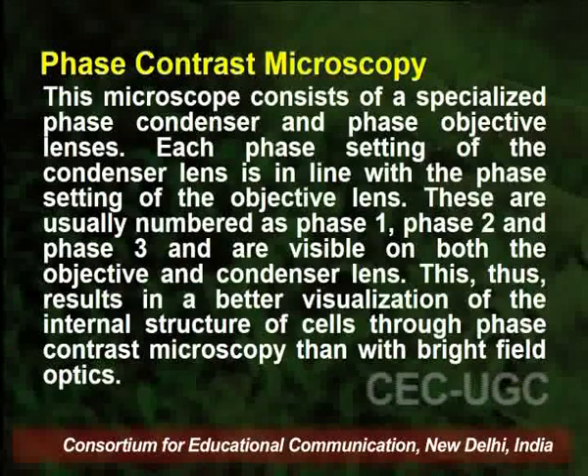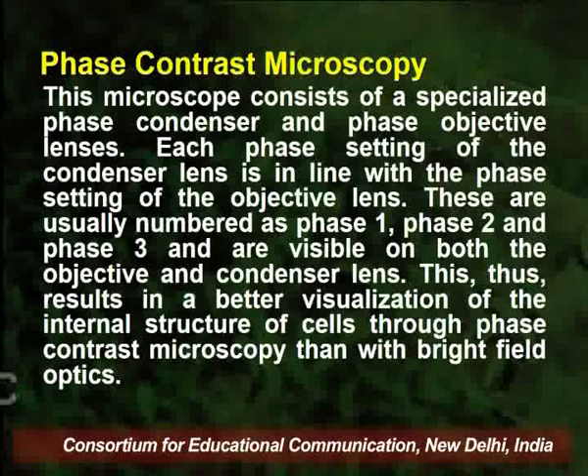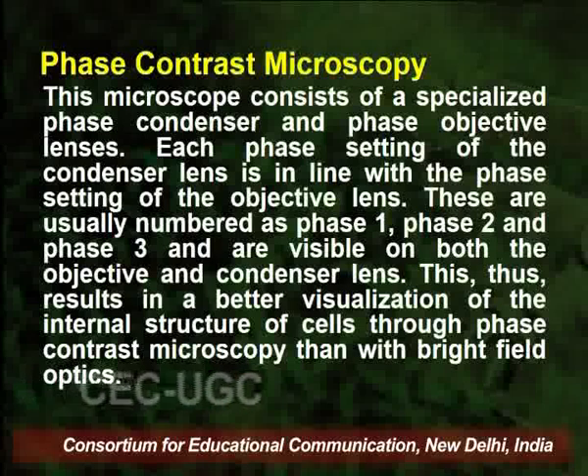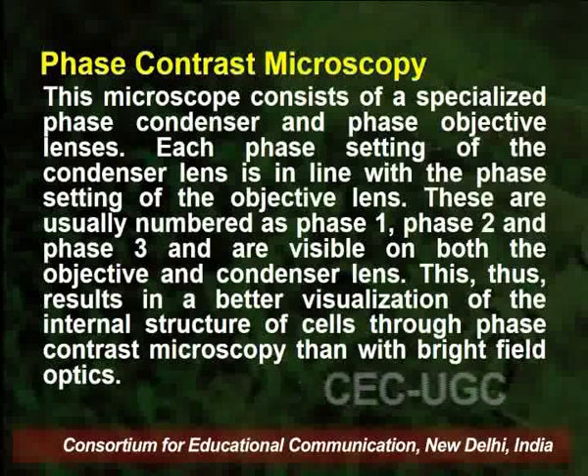A phase contrast microscope consists of a specialized phase condenser and phase objective lenses. Each phase setting of the condenser lens is in line with the phase setting of the objective lens. These are usually numbered as phase 1, phase 2, and phase 3, and they are visible on both the objective and condenser lenses. This results in better visualization of the internal structure of cells compared to bright field microscopes.